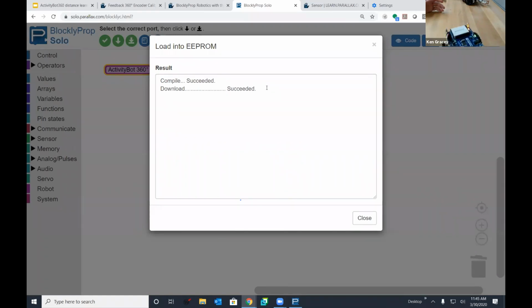An important part of going through its process is you'll be waiting for it to complete all those maneuvers Ken is showing you right now, but there will also be a pair of yellow lights below the white board on it. Those yellow lights will stay on for a little while after it has completed its maneuvers. You have to wait until those yellow lights turn off, like they just did, before you can turn the power off. Otherwise, the calibration won't be completely saved.